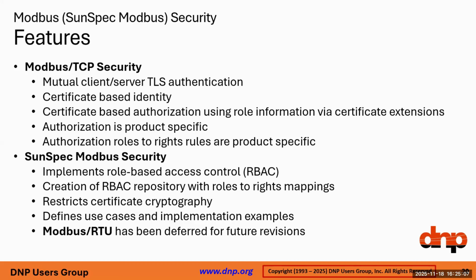For SunSpec, they do a very good job providing device information and profiles, with mappings even to IEEE 1547. They're really looking to complement that. IEEE 1547 kind of punted on security - I forget the exact wording, but they basically use general wording like 'no matter what you use, you shall be secure.' So they really tried to address that here through the use of certificates and cryptography to embed some role-based access controls.